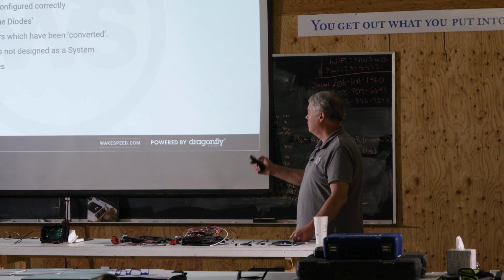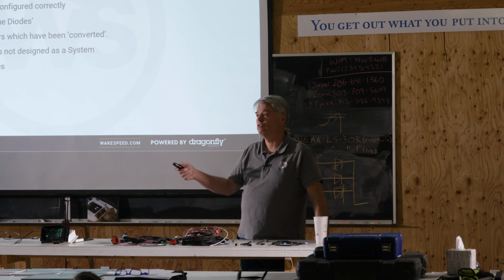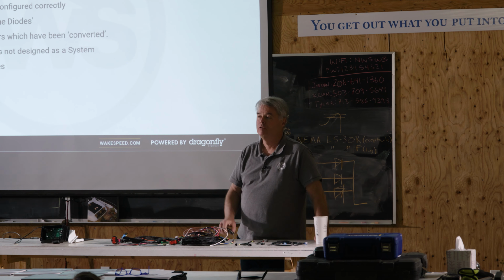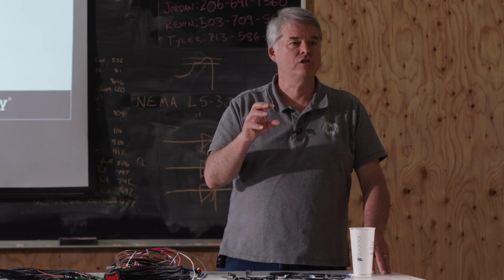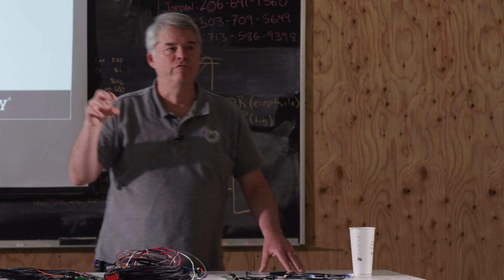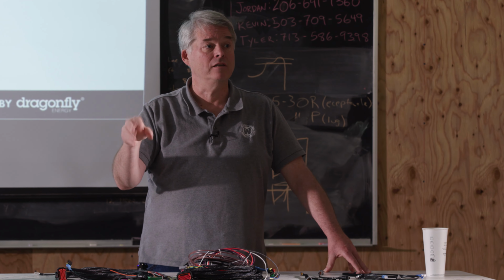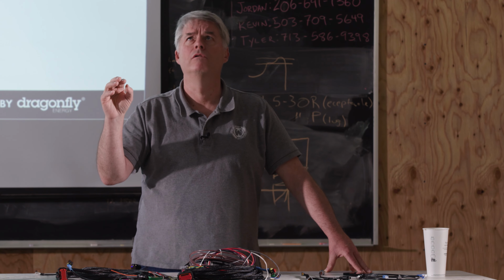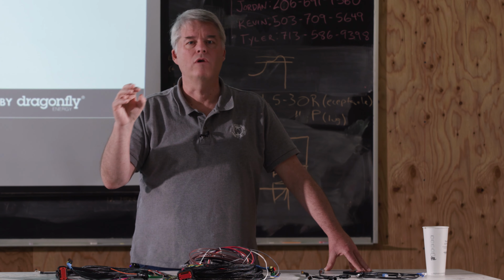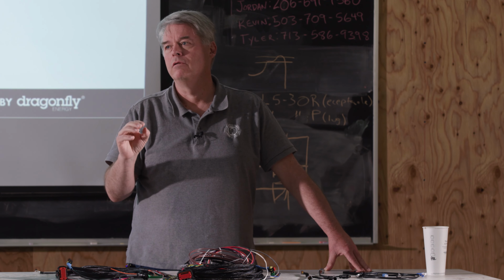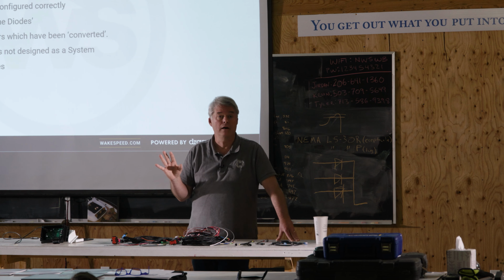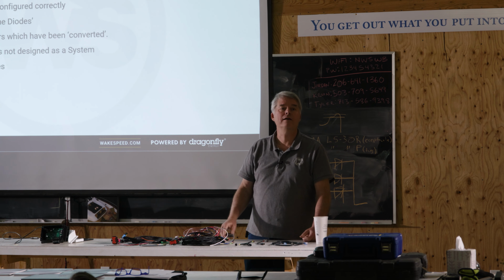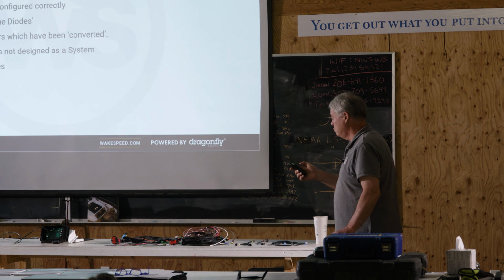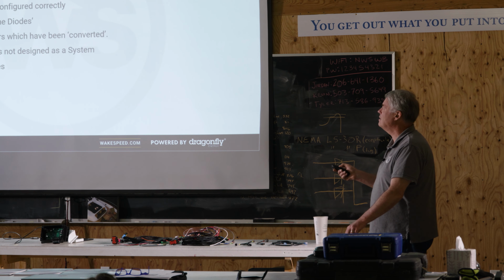Alternators without surge suppression - I'll make a little comment. This technology does not exist for 48 volts. The whole transportation industry hasn't solved this issue for 48 volts yet. As a matter of fact, for 12 and 24 volts, the ISO standards say avalanche diodes is the best protection. For 48 volts, there is a standard. It simply says, thou shalt never have more than 68 volts, I think is what they say. You have to design your system to prevent overvoltage, which is what we do with our batteries that we have a good integration with. So it's not important now, but as you move forward, just know that's not a thing today.